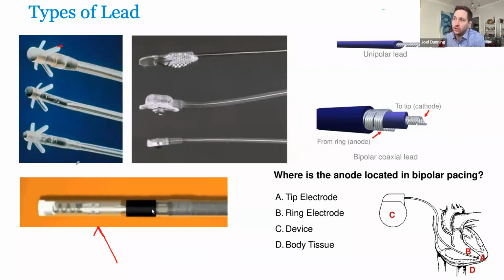So the way these function is you have your tip electrode at the distal end, and then you have a more proximal electrode, or you use the can as your anode. So your cathode will typically be your tip, and then your anode will be the source to where the electrons flow. In this case, here's your ring electrode. You'll pace from the tip, the cathode, negative, and then it'll move to the positive. Older leads didn't actually have bipolar capability. Bipolar is relatively new, in the last couple of decades, but conventional leads are mostly bipolar now.